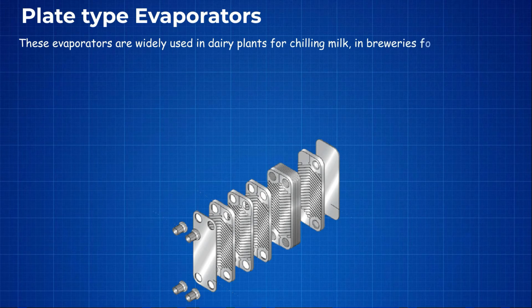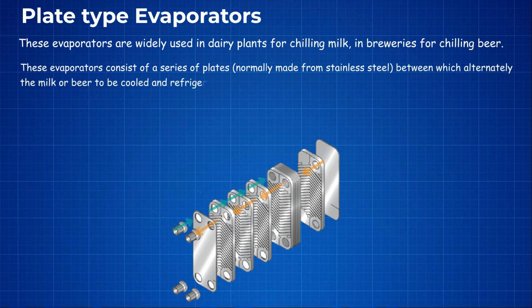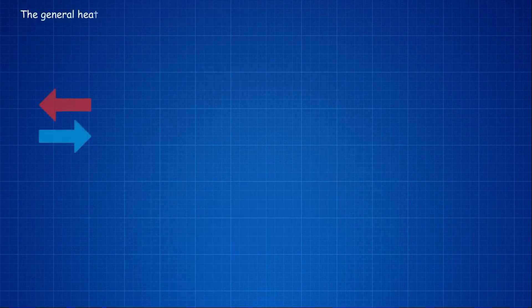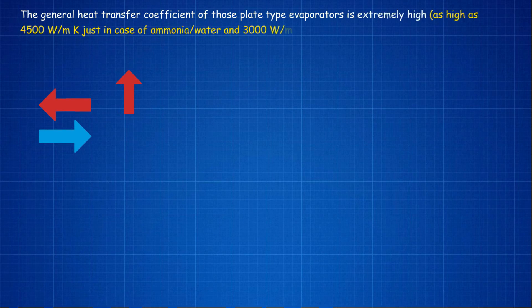Plate type evaporators are widely used in dairy plants for chilling milk and in breweries for chilling beer. These evaporators consist of a series of plates, normally made from stainless steel, between which alternately the milk or beer to be cooled and refrigerant flow in counterflow direction. The overall heat transfer coefficient is extremely high — as high as 4500 W/m²K in the case of ammonia or water, and 3000 W/m²K in the case of R-22 per water.